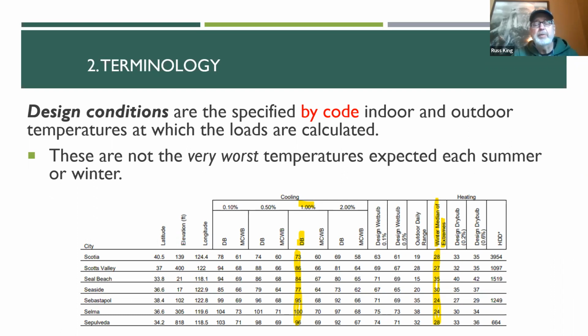And a lot of people are a little thrown off by the outdoor design temperatures, and they'll look at them and say, well, that's not the coldest day I remember it being, and it's not designed for the coldest day. You don't want to design for the coldest day, and you don't want to design for the hottest day. For cooling, we're designing to what's called the one percentile, which means 1% of the time it's actually hotter than that number, okay? And then there's another number we use for heating.